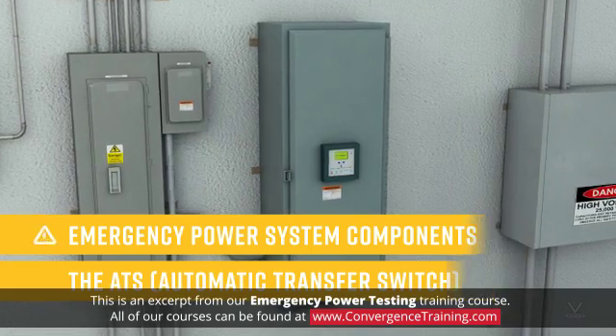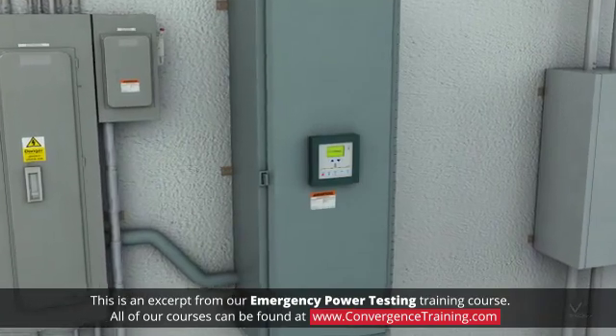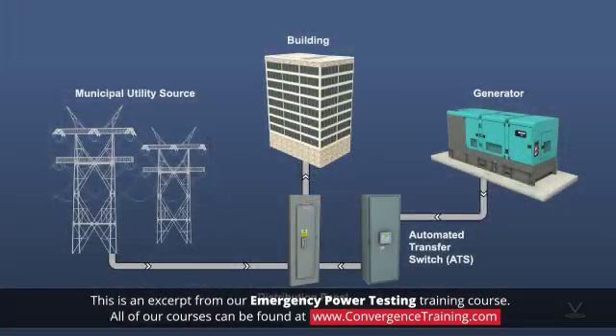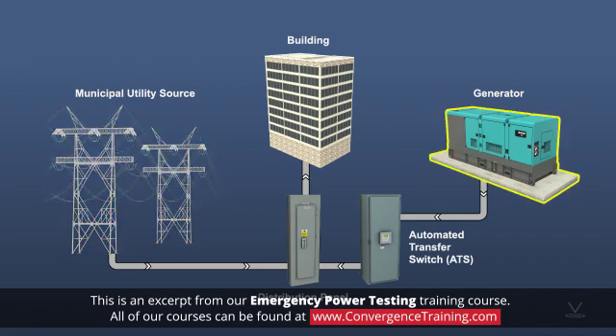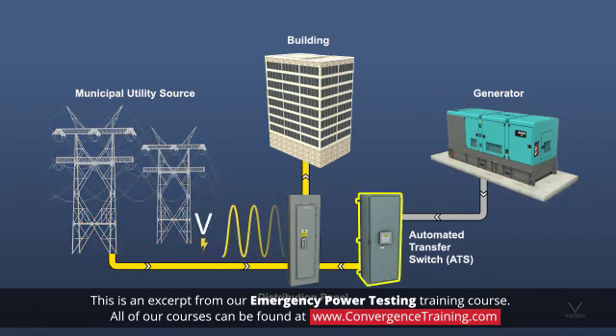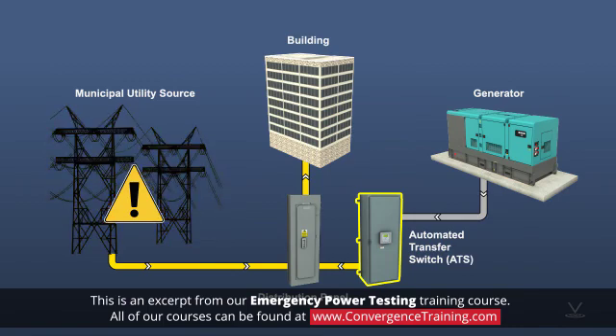The automatic transfer switch is a smart electromechanical device intended to automatically switch a load from the usual utility-supplied power over to generator-supplied power. These switches monitor utility-supplied voltage and, when the voltage drops below an average operating level for a predetermined period, usually 20 to 30 seconds, the following sequence takes place.